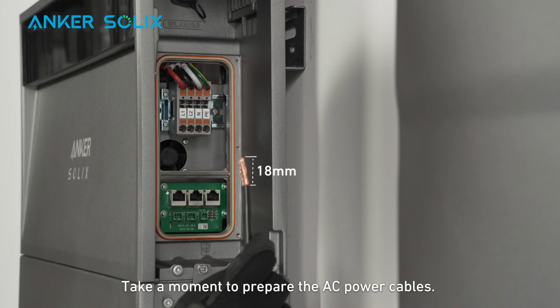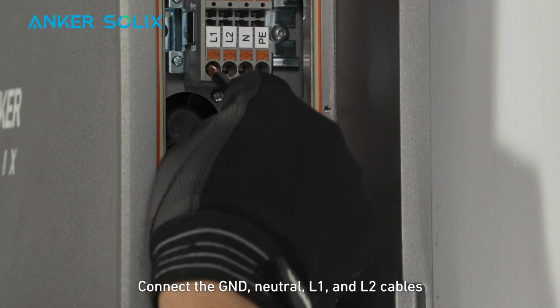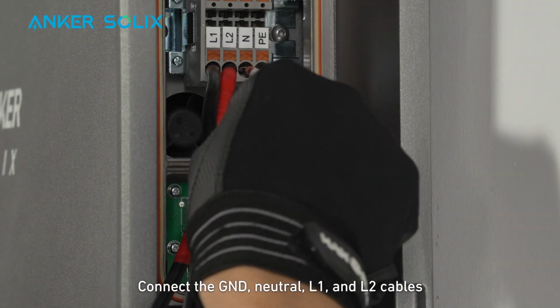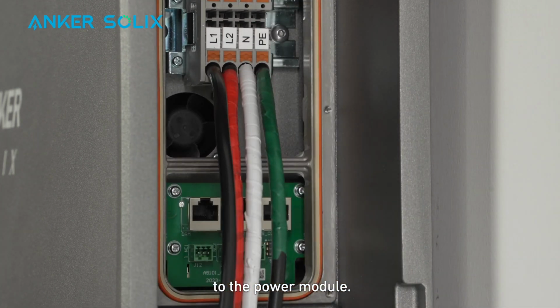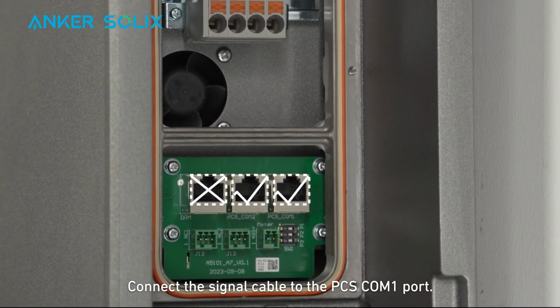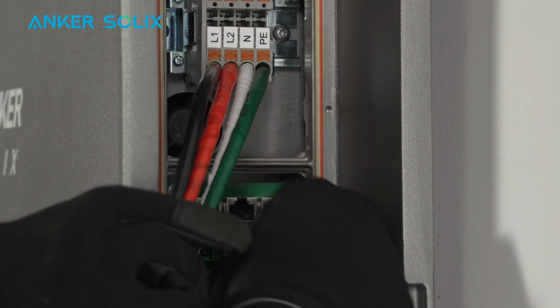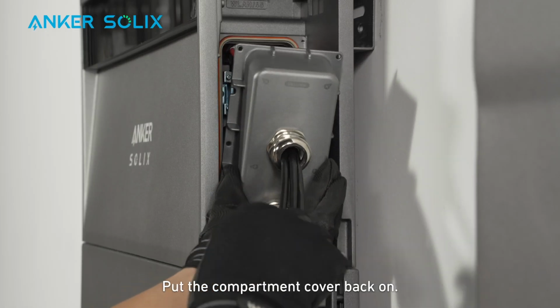Take a moment to prepare the AC power cables. Strip 18 mm of insulation. Connect the ground, neutral, L1 and L2 cables to the power module. Connect the signal cable to the PCS COM1 port. Put the compartment cover back on.